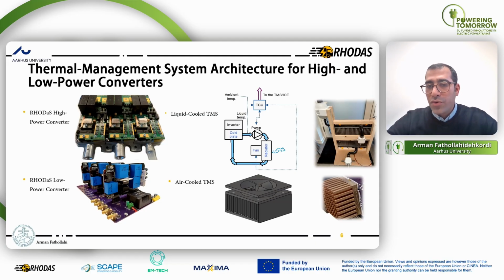In the liquid-cooled thermal management system, you have your power converter, and after that a heatsink or cold plate, coming through a pump, a radiator, a fan, and a circulating liquid that is usually 50% glycol and 50% water. This controls the junction temperature of the different semiconductors and modules. You also have a control unit, which gives you the opportunity to control the flow rate and pump speed of the system.